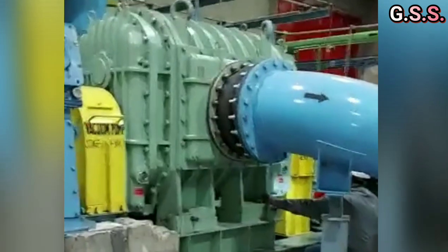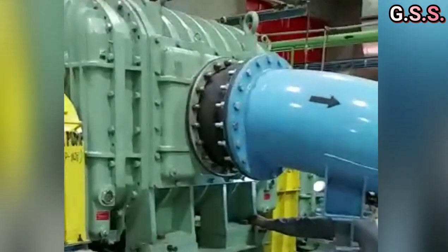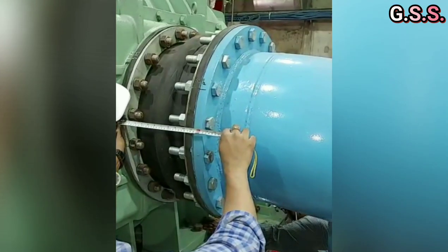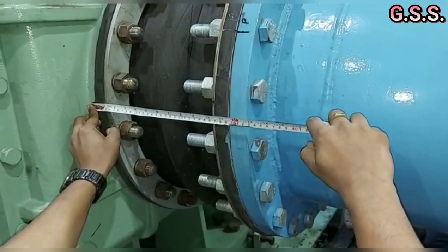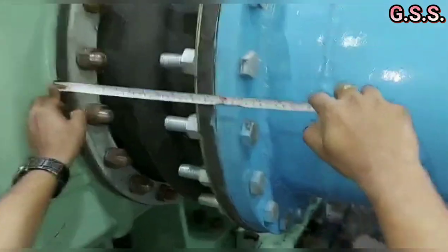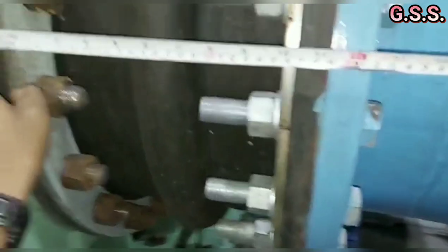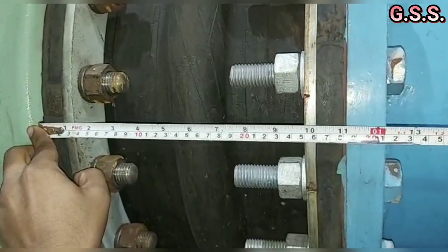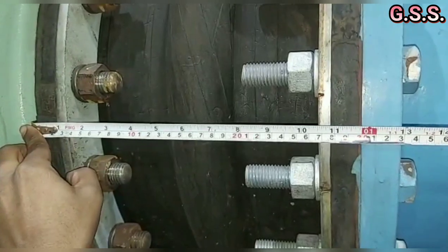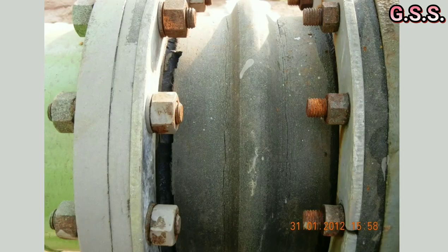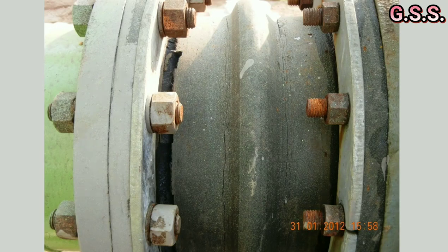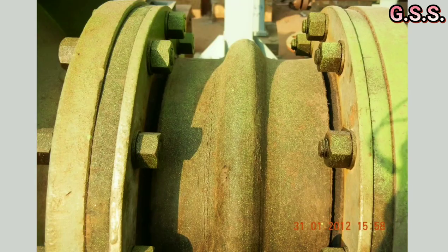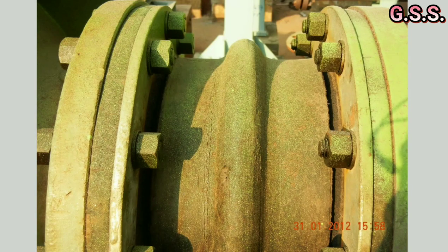Also due to axial stretching of the bellow, bellow may tear off. Once again you can see how the bellow expands axially due to internal pressure. In this way rubber bellow fails and after failure rubber bellow looks like this.